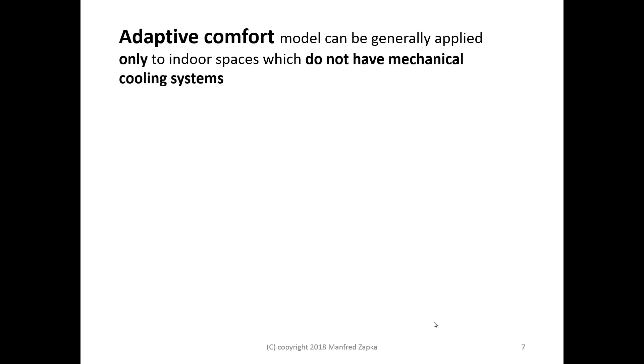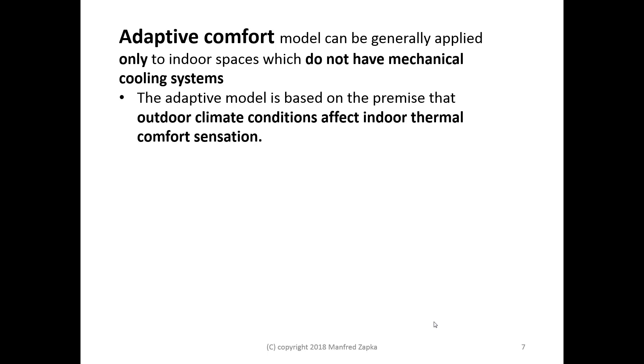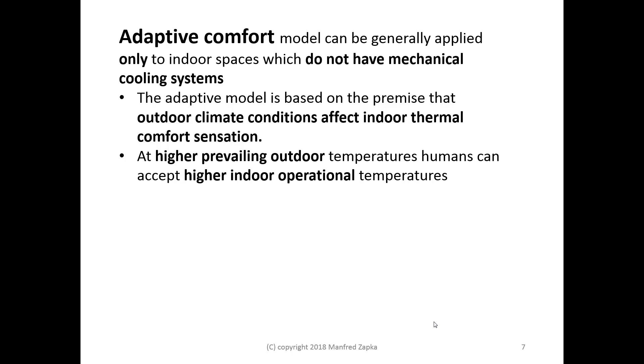The adaptive comfort model can generally be applied only to indoor spaces which do not have a mechanical cooling system. Adaptive comfort is based on the premise that outdoor climatic conditions affect indoor thermal comfort sensation. The higher the prevailing outdoor temperature, the higher the indoor operational temperature humans can accept — people adapt to warmer conditions and can have acceptable thermal comfort at higher indoor operative temperatures.